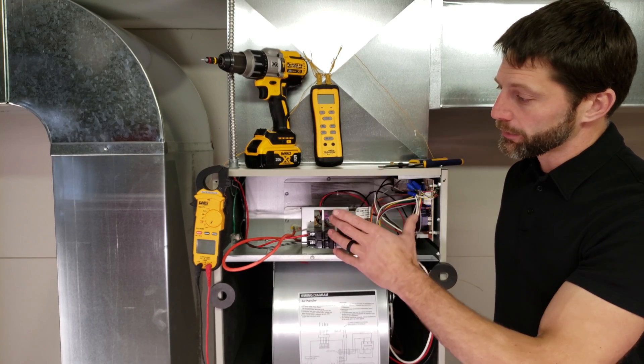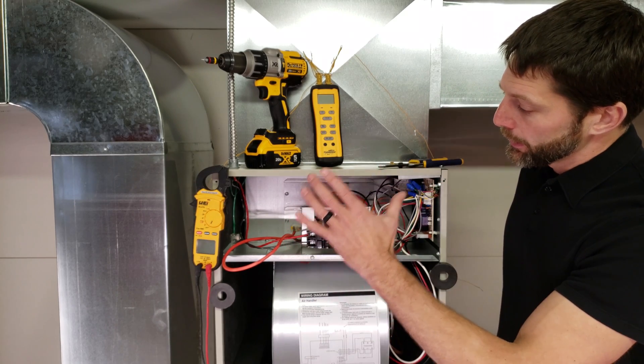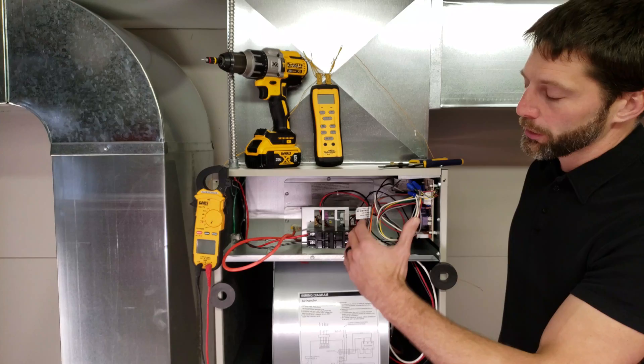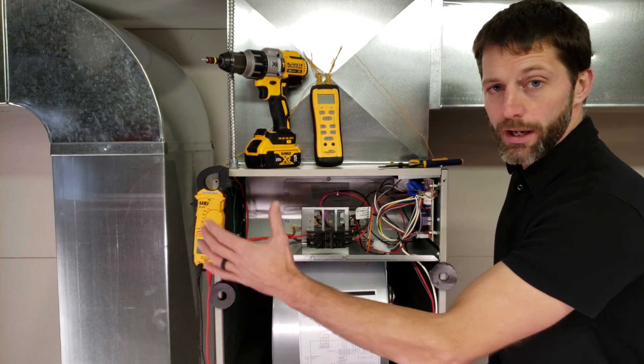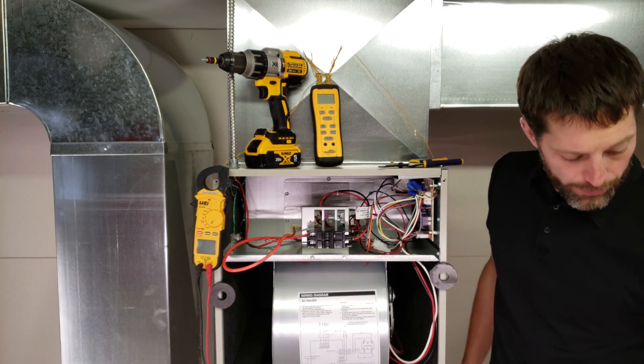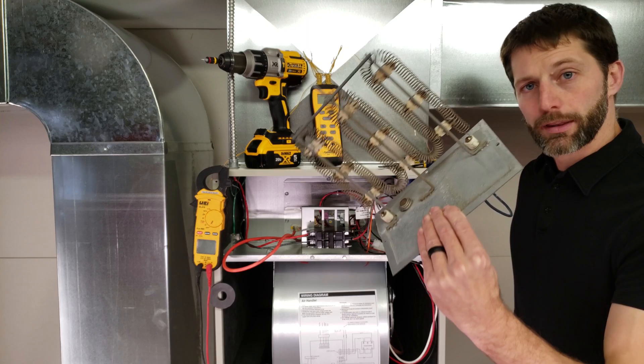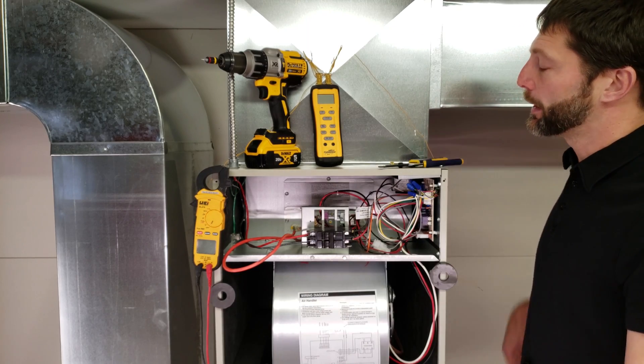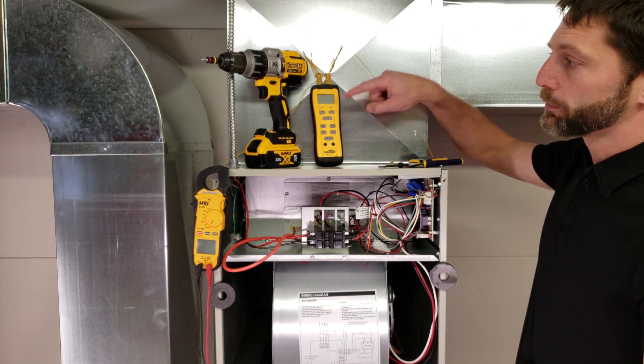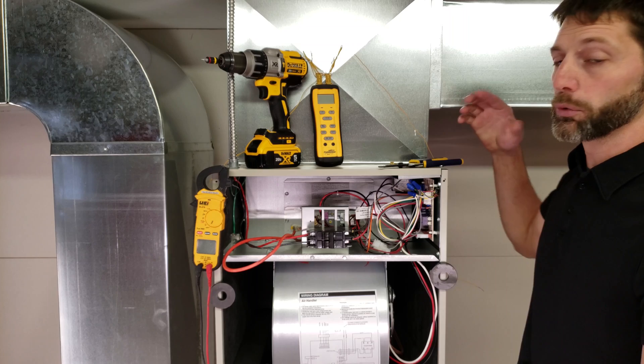So we're going to be measuring the CFMs of this system right here, but what we're going to be doing is we're going to be measuring the voltage and the amperage on the electric strip heater, and the strip heater looks just like this, and we're going to also be reading our temperature rise from the return duct to the supply duct in order to figure this out.